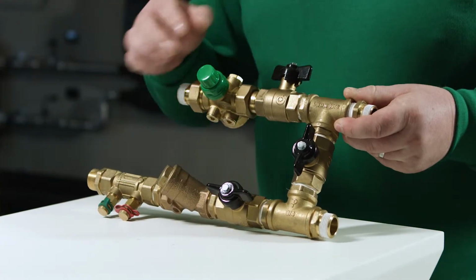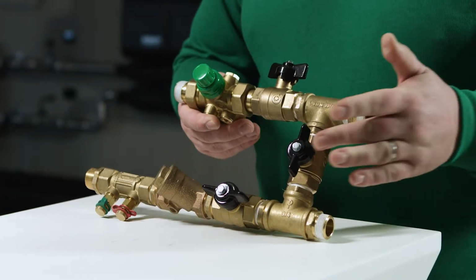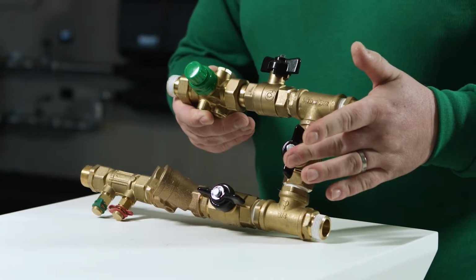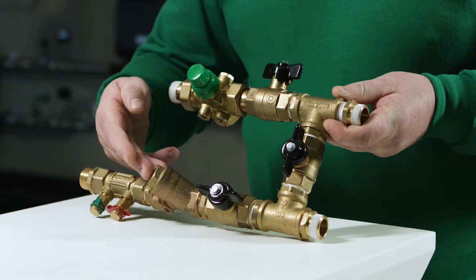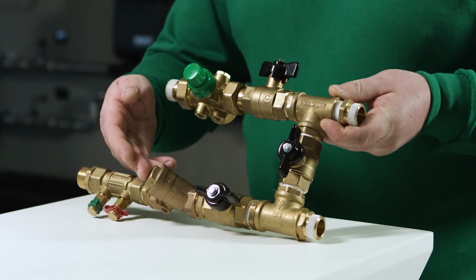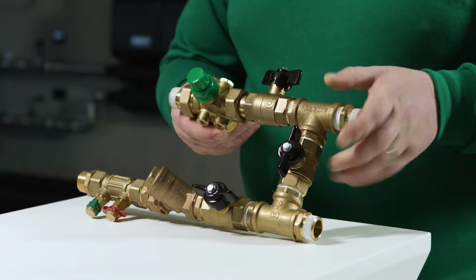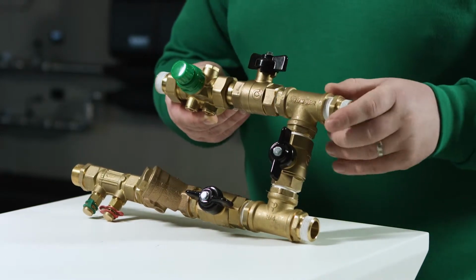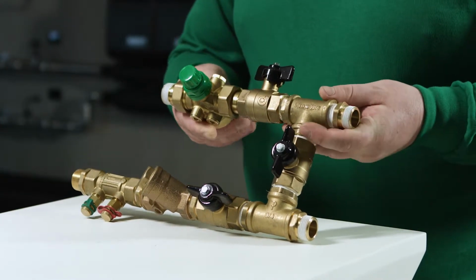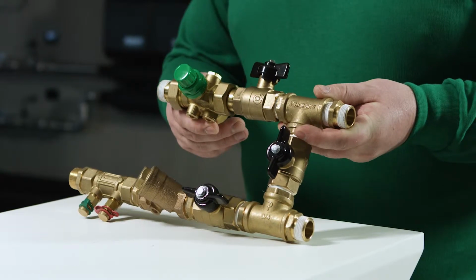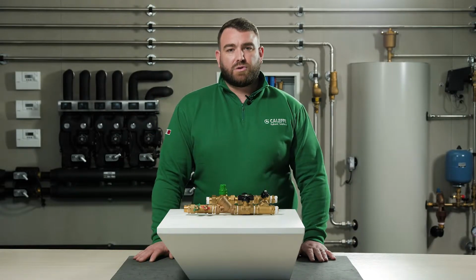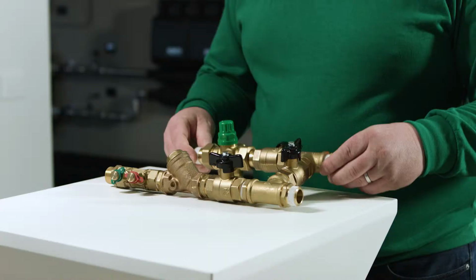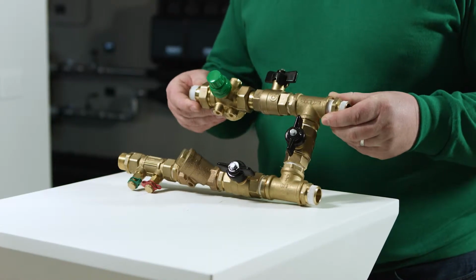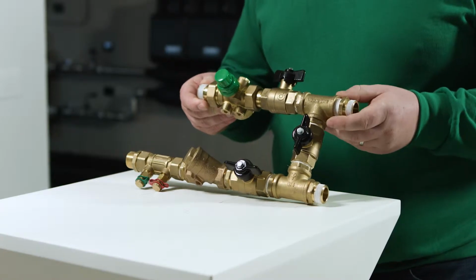2 shut-off valves to isolate the terminal unit, 1 shut-off valve to control the bypass line, 1 Y-pattern strainer to prevent dirt from entering the terminal unit, 1 balancing valve to control the flow rate inside the terminal unit, and a zone valve for the remote control. All of these connections together mean that we have 20 hydraulic connections in the unit. This means a greater space for installation, but also a longer time for the installer.